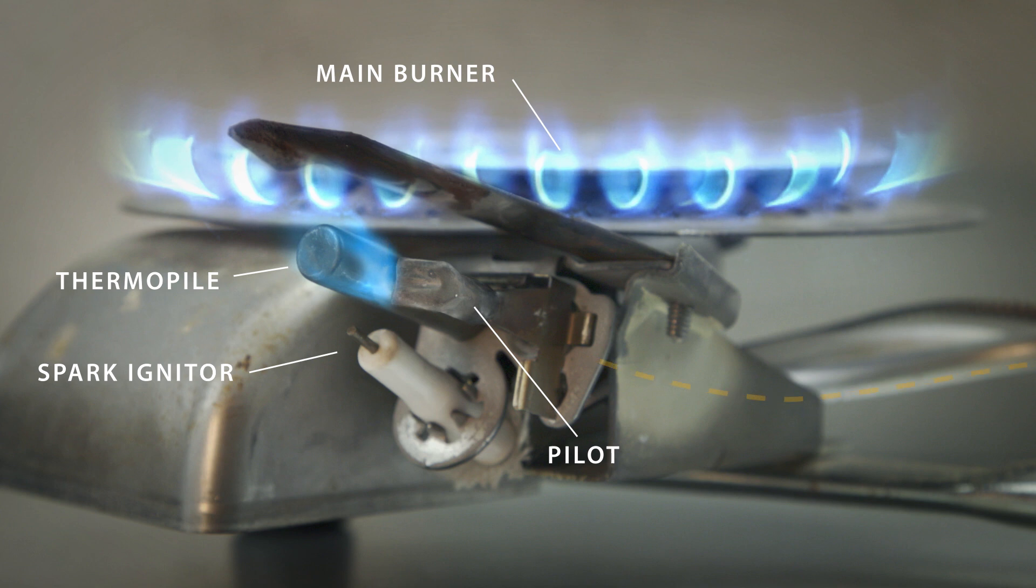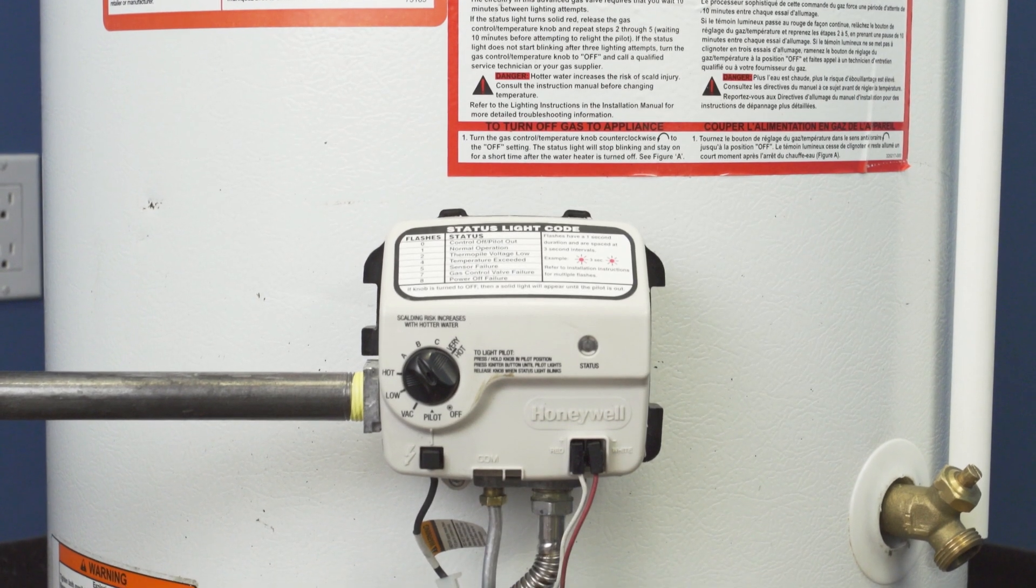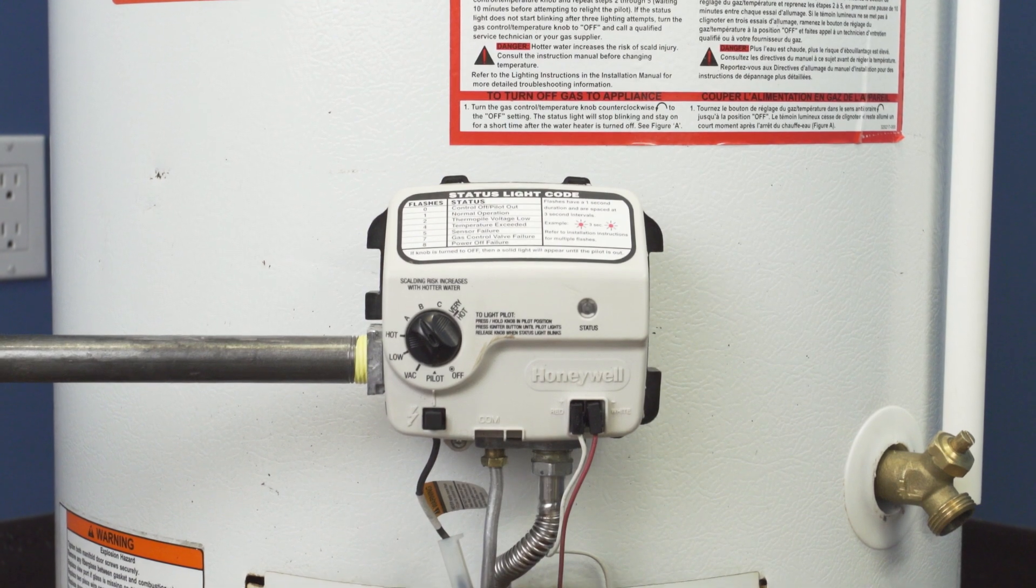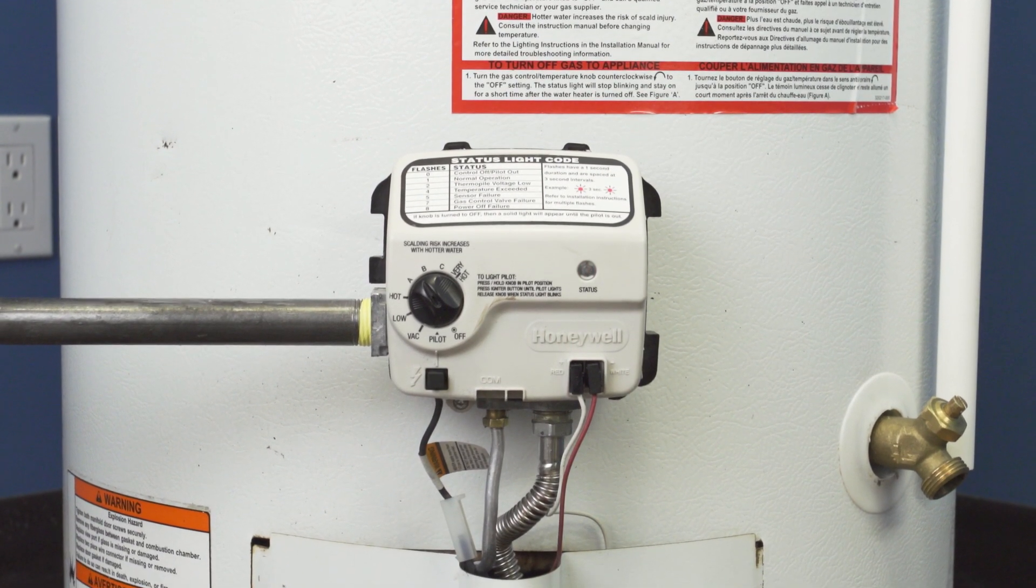Next to the pilot is the thermopile, which generates a small electrical current when heated by the pilot flame. This produces less voltage than a AA battery, but enough to power the electronic gas valve and diagnostics.